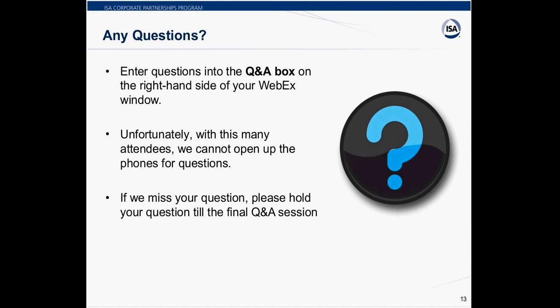Next question: is a HART communicator the only calibrator we can use to calibrate? You need something with a HART communicator to calibrate HART. For example, the Fluke 754 does support the universal commands but not the proprietary ones, so you can do some of the commands. But you need something that will source and measure, and then something that can do the communication to do the trimming functions.